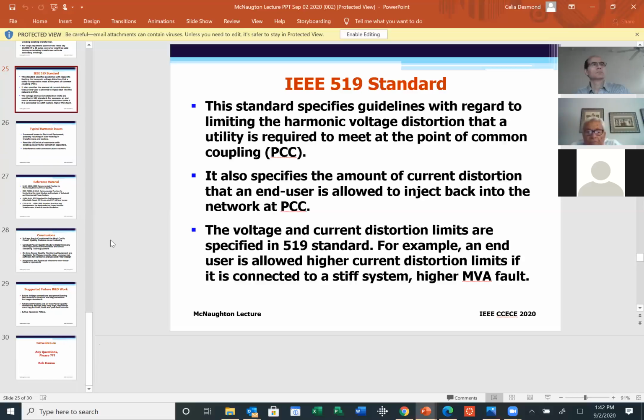So it puts a limitation so that the onus is on the utility to make sure that the waveform they provide is within certain limits. At the same time, it turns around to the end user, puts another limitation on the end user, and tells them what current distortion limits they can inject. Imagine you have a river and polluters. If you were polluting, let's exaggerate here, in a lake, then the impact is not the same as if you are polluting in a river. I'm not suggesting you go around polluting, but I'm just giving you a sense of the differences between these two. Next slide, please.